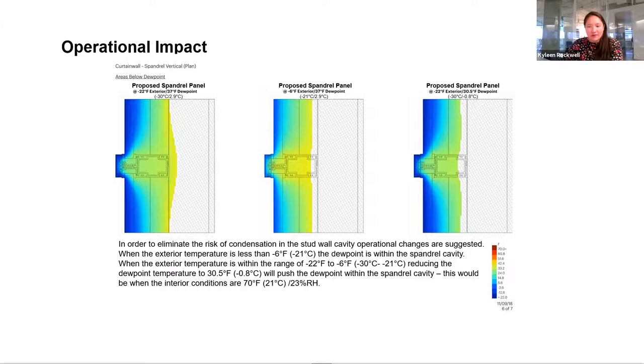This starts to really inform an operational strategy for the engineering team or facilities team: when the temperature is below negative 6 degrees Fahrenheit, they should be dropping their dew point temperature to ensure no condensation occurs. We were on live Zoom meetings with team members, adjusting boundary conditions live and playing around with insulation options, with quick feedback on what would be possible for the design or not.